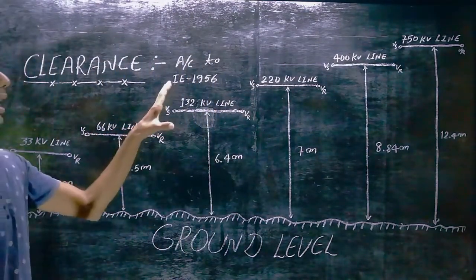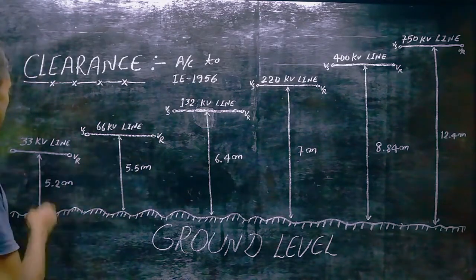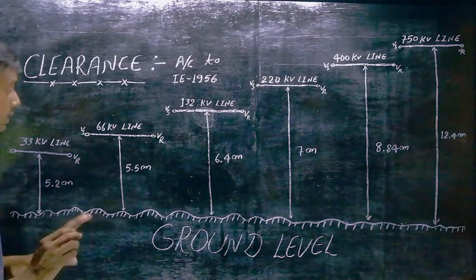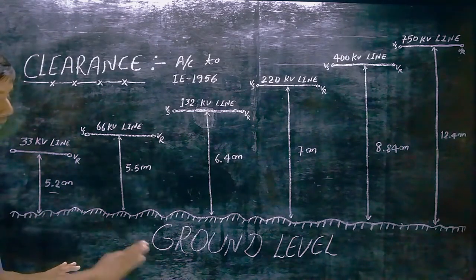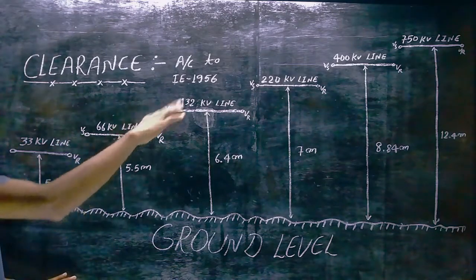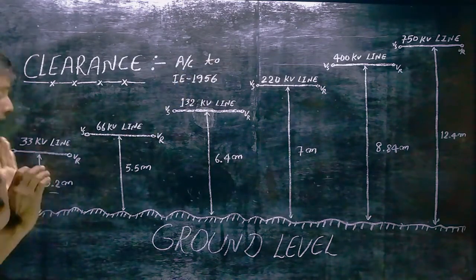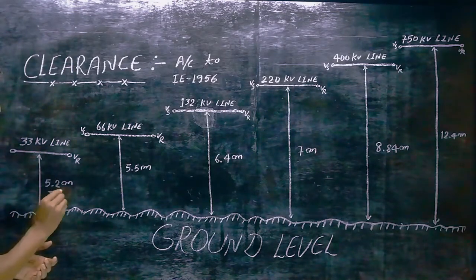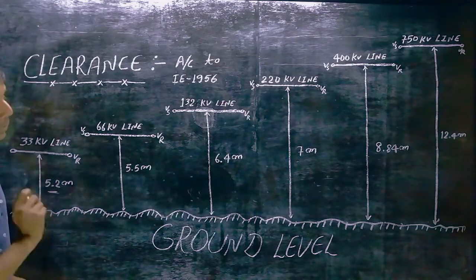I have taken the clearance values here as per IE 1956 rules. I have shown you the ground level and classified the transmission voltage levels. For 33 kV lines, the distance between the transmission line and ground level is 5.2 meters.